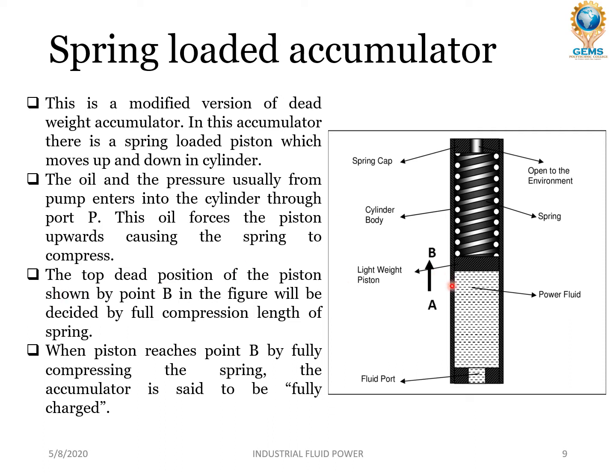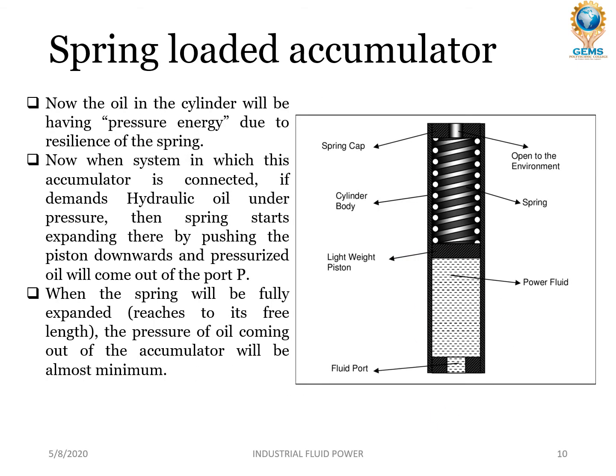The incoming oil forces the piston upwards, causing the spring to compress. When high pressure oil enters, it makes the piston move upward so that the spring gets compressed. The top position of the piston, shown by point B in the figure, is decided by the full compression length of the spring. When the piston reaches point B by fully compressing the spring, the accumulator is said to be fully charged. The oil in the cylinder now has pressure energy due to the resilience of the spring.